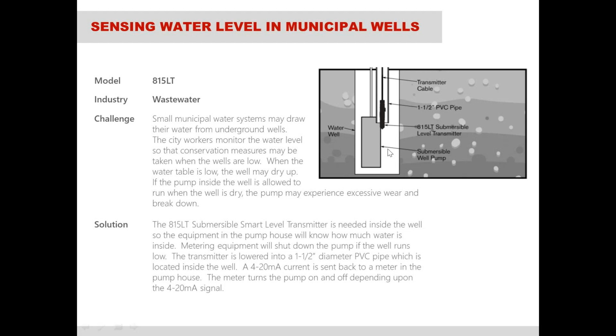This is important to monitor the level of that well, because if the level starts to get too low, the city or the town can start conservation methods to prevent that well from going down too much, or it can alert them to make sure that they don't operate that pump without any liquid there. If you run the pump and it's just air going through that pump, that can severely damage the pump and you'll probably have to replace it.